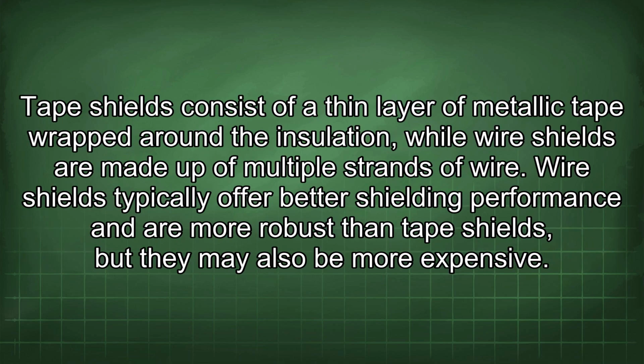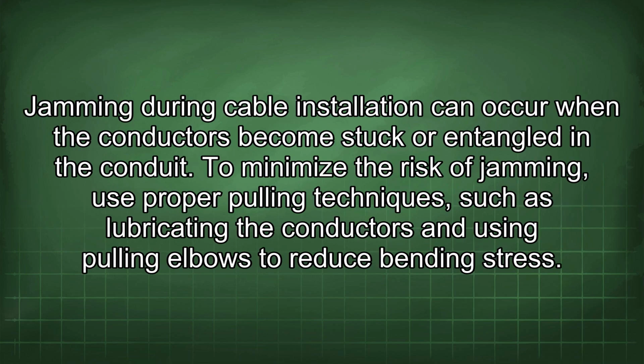Tape shields consist of a thin layer of metallic tape wrapped around the insulation, while wire shields are made up of multiple strands of wire. Wire shields typically offer better shielding performance and are more robust than tape shields, but they may also be more expensive. Jamming during cable installation can occur when the conductors become stuck or entangled in the conduit.